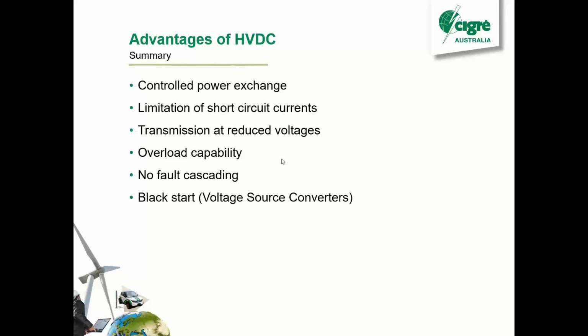With HVDC, you can do the overloads. Our system's got some pretty good overloads to deal with loss of a pole in bipolar operation. The remaining pole can overload to try and take up that power. Also, you get no fault cascading, that's when faults can cascade through an AC network, but with HVDC, if it's designed correctly, you can stop it at one end. So, for example, if we had a collapse in the North Island, it shouldn't affect the South Island, as long as the controls are done correctly. And yeah, the other advantage is black start, but you can only do that with the voltage source converter, not with LCC.